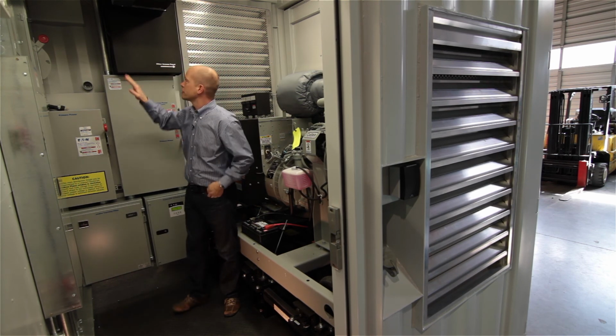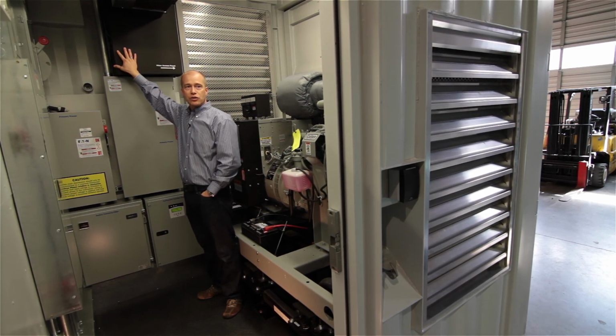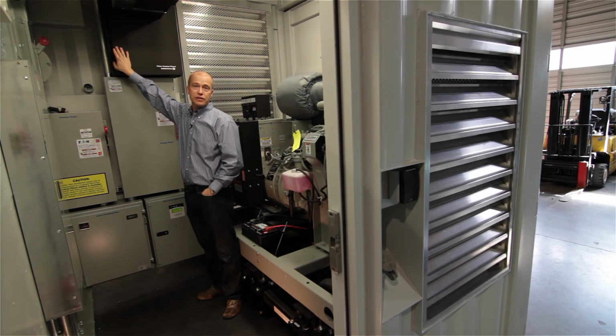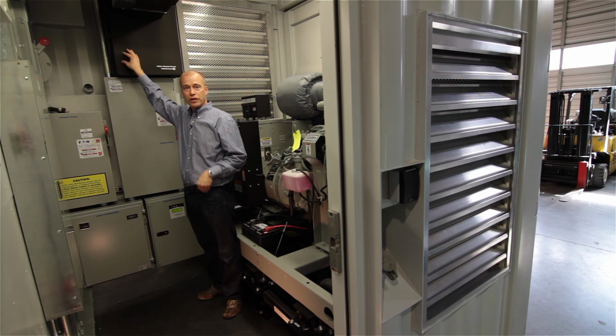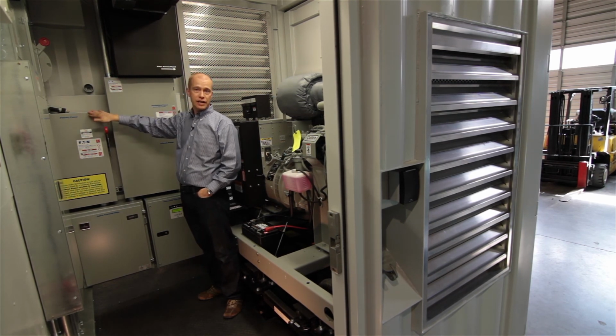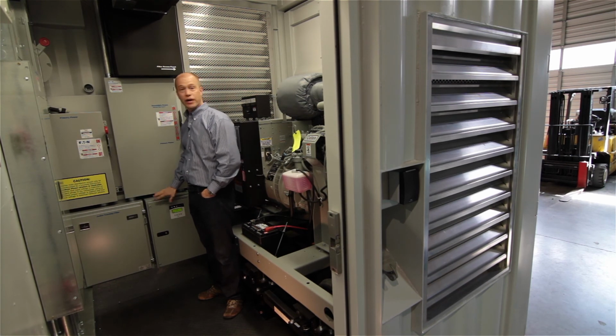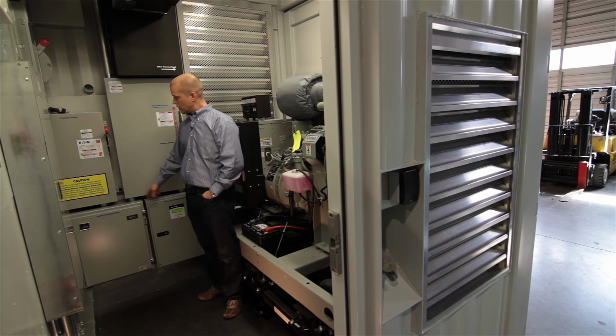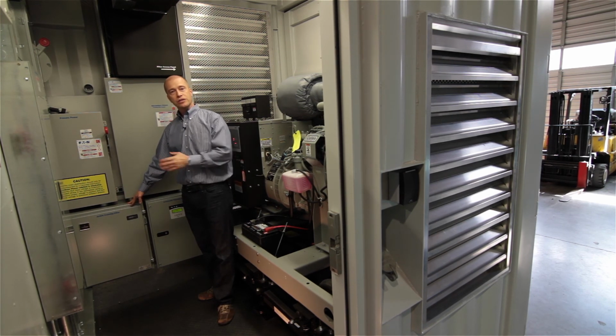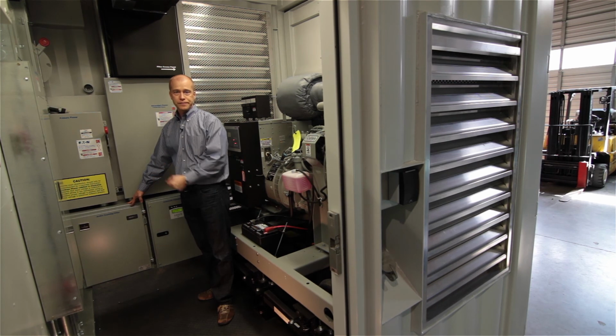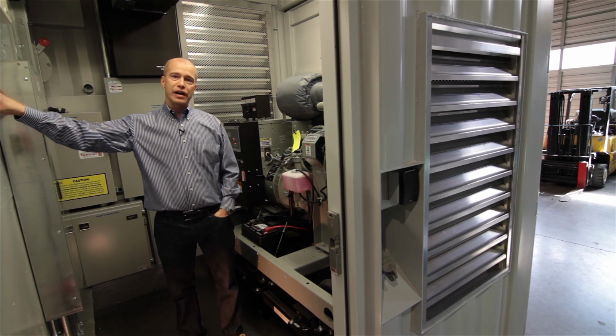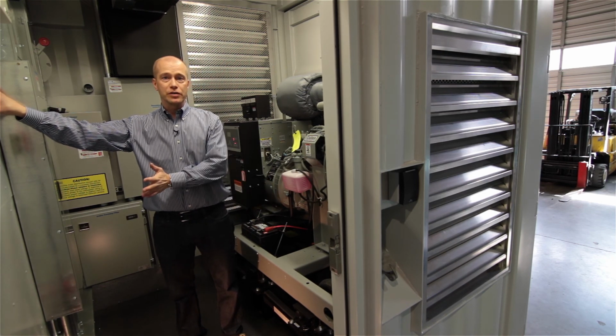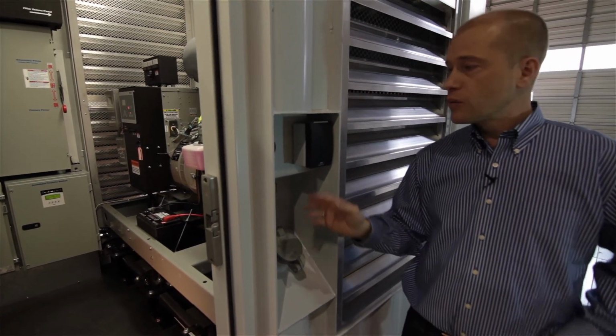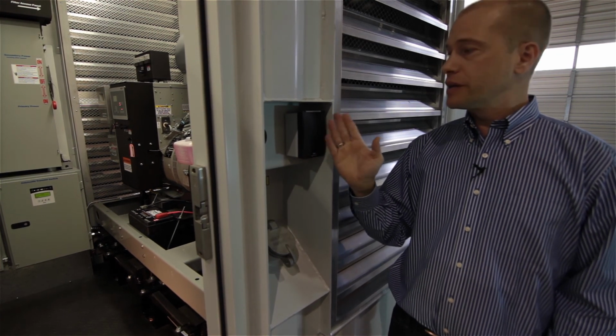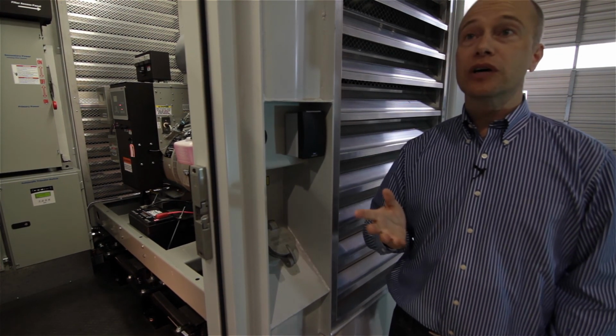We even go so far as to monitor the makeup air filter. On the filter, we have pressure sensors on either side of the filter. When the pressure differential is too much, then we know that it's time to change the filter. We also have primary and secondary power inputs. These are all tied together with an automatic transfer switch, which is also highly monitored remotely. We've also installed an active tracking filter, which is designed for the mining industry. We also have a 1-hour fire-rated wall that separates the electrical room from the rest of the unit. Outside, we have the external fuel fill, we have a manual gauge, and we also have the card security access. Why don't we go look at zone number 2.